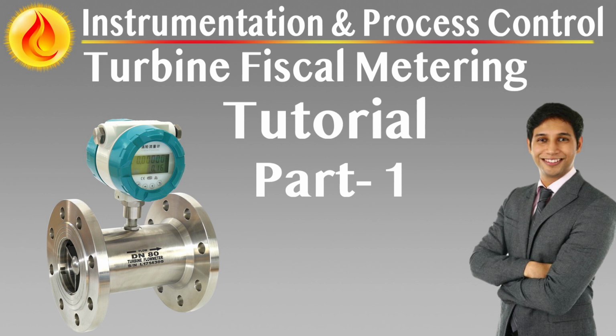Inlet header configuration and instrumentation design. Measurement boundary and system initiation. The inlet header defines the upstream measurement boundary and establishes the metering system's baseline conditions. It is not merely a flow entry point. It is the convergence zone for pressure, temperature, and sample stream instrumentation that anchors the metering logic. The accuracy and reliability of these measurements have a direct influence on calculated mass, density corrections, sampling quality, and ultimately custody transfer validity.